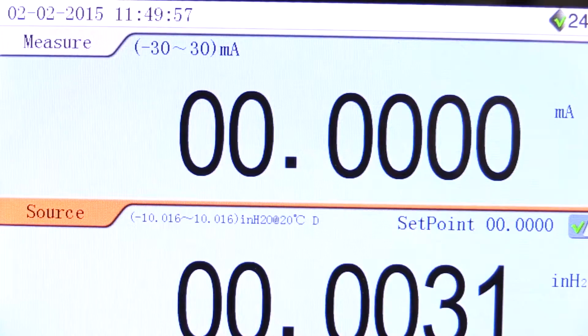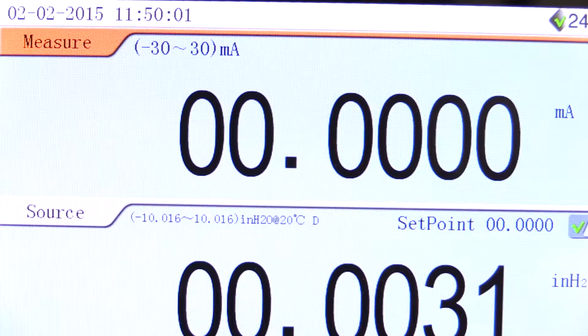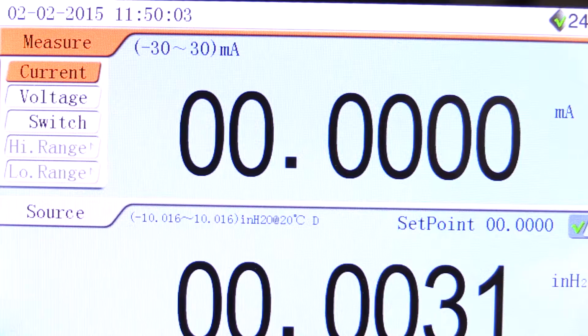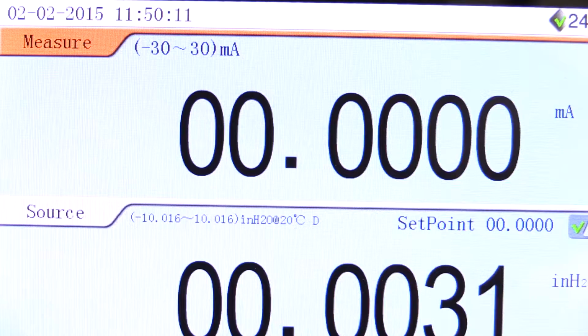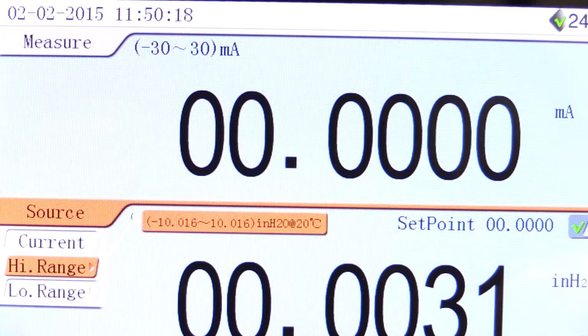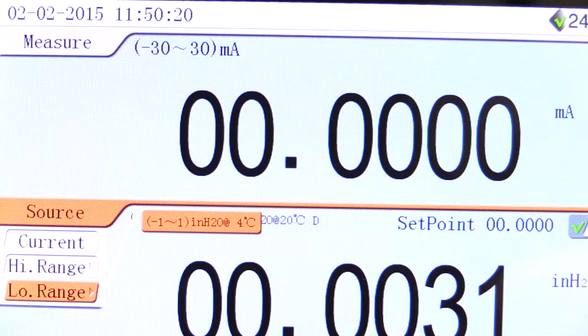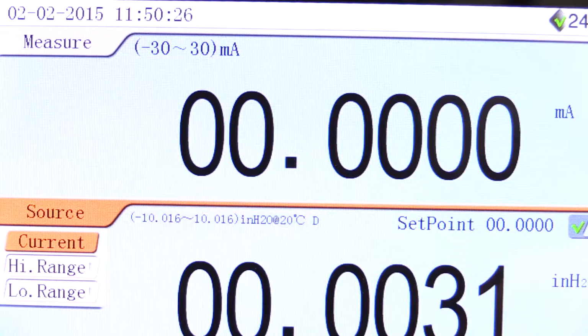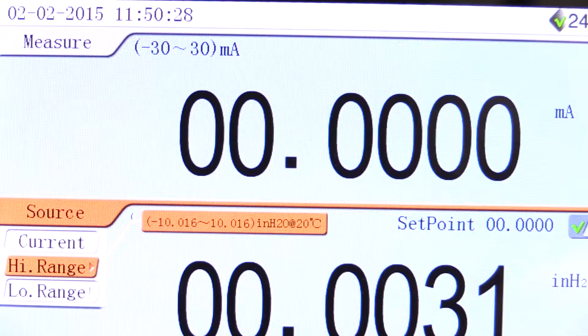The ADT761 has a split screen that shows measure and source windows. In the measure window, by selecting measure, the appropriate setting is selected to read the transmitter. In this case, current is the selection we need. In the source window, select source and ensure the appropriate sensor range is selected for the device under test. In this case, plus or minus 10 inches of water is the best selection for this transmitter.